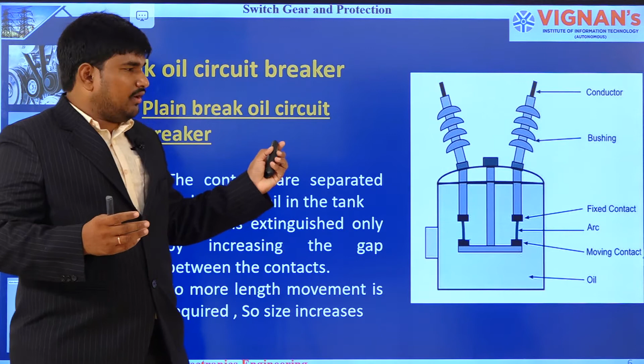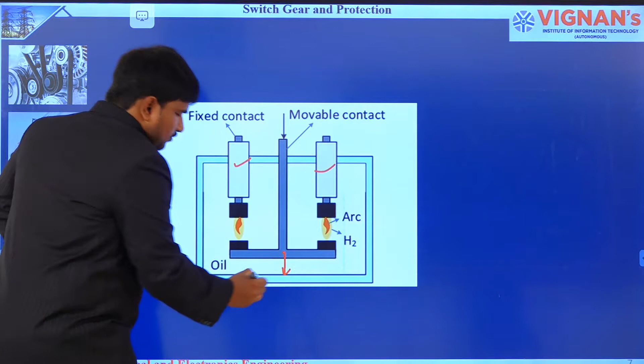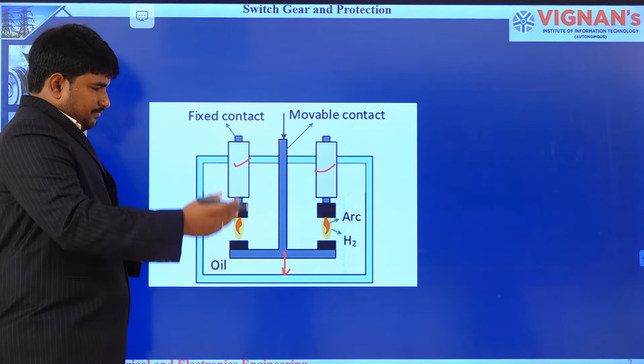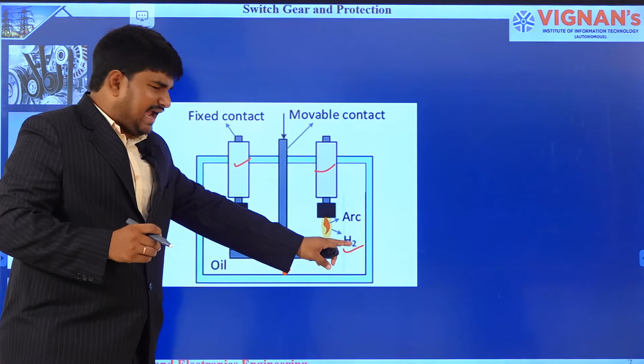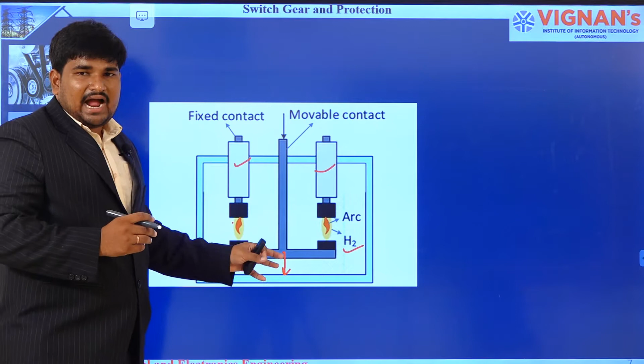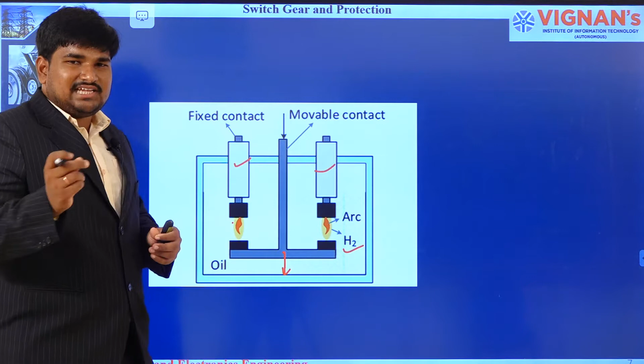Observe here, this is the fixed contact and this is the moving contact. When the moving contact moves away from the fixed contact, there is a production of arc. Because of this arc, the oil around it is heated up. This heated oil vaporizes into hydrogen and small quantities of methane, ethane and carbon particles. This hydrogen cools the arc, provides high dielectric strength to the gap, and easily quenches the arc.